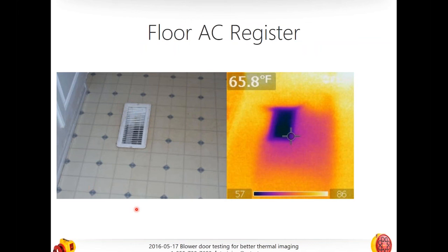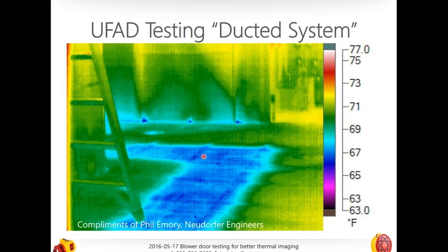Here we have a floor register over an unconditioned cellar or crawl space. The boot — the connection from the duct work — is not connected securely to the floor, and it's actually pumping warm air into the floor cavity. Here's another great image — a UFAD, or under-floor air distribution system in a commercial building, compliments of our friend Phil. We used a blower door on the duct system to pressurize it, then used an infrared camera to see how leaky it is.